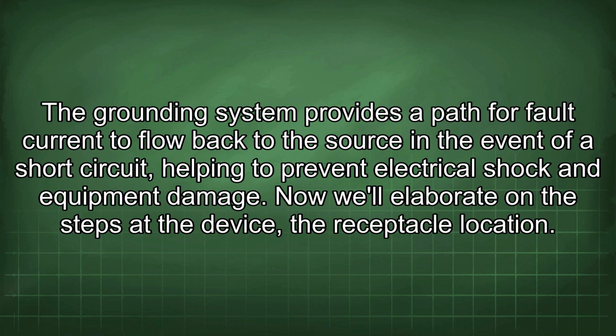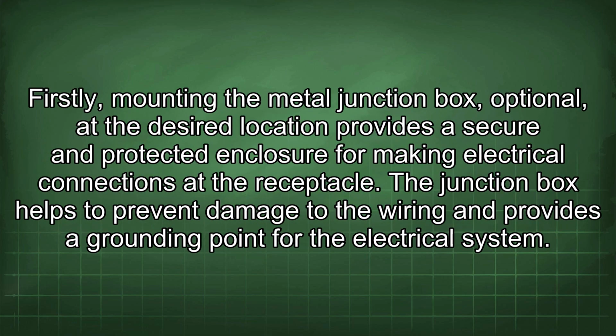Now we'll elaborate on the steps at the device, the receptacle location. Firstly, mounting the metal junction box, optional, at the desired location provides a secure and protected enclosure for making electrical connections at the receptacle. The junction box helps to prevent damage to the wiring and provides a grounding point for the electrical system.